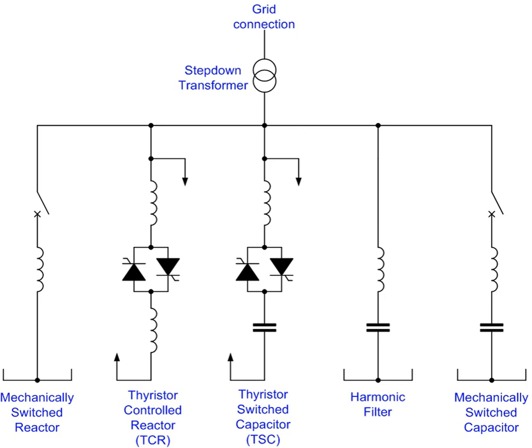Topic: Connection. Generally, static VAR compensation is not done at line voltage. A bank of transformers steps the transmission voltage, for example, 230 kV, down to a much lower level, for example, 9.0 kV. This reduces the size and number of components needed in the SVC, although the conductors must be very large to handle the high currents associated with the lower voltage.